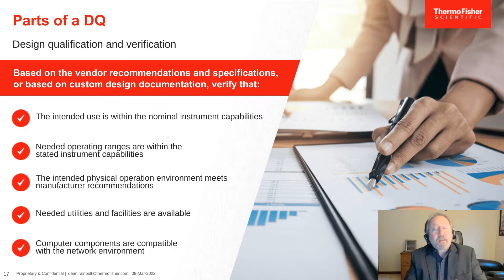Now let's go to design, qualification, and verification. Based on the vendor recommendations and specifications, or based on custom design documentation, you want to verify that the intended use is within the nominal instrument capabilities. You also need operating ranges, and you want to verify they're within the stated instrument capabilities. The intended physical operating environment needs to meet the manufacturer's recommendation. You need to check the utilities and facilities and make sure the proper stuff is available, and also that computer components are compatible with your network environment. So your quality group and your IT group really need to be on board before you order this freezer.